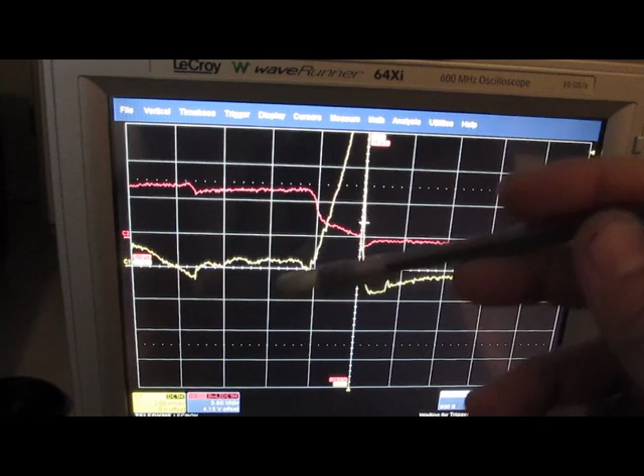If we zoom in and look at the high frequency pulse here, again this is our high voltage. You can see here it rises fairly linearly and eventually it arcs over. And then you can see the rapid decline before we go into the ionization phase. Right now we're looking at 5,000 volts per division. You can see we're putting out about 10,000, 15,000 volts right now with the gap the way it's set.